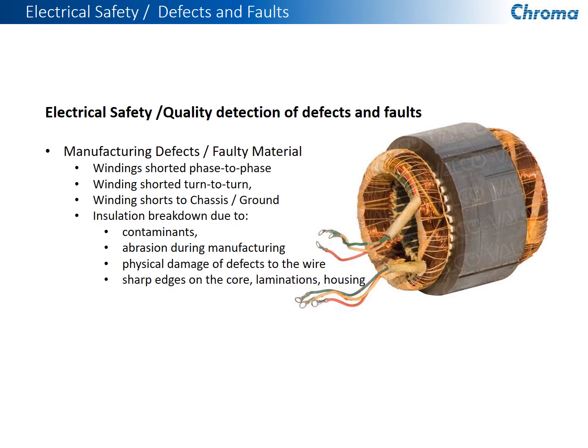So things that can happen during manufacturing defects, you can have everything from faulty material, the actual wire itself, its insulating material can have some kind of a fault in it. You can find material fault in the actual tape and the actual material used for insulation. There can be things like windings shorted phase to phase, internal windings shorted turn to turn, windings shorted to the chassis or ground or core, and various other types of breakdown due to some type of contamination within the windings, abrasion during manufacturing, physical damage, defects to the wire during storage, sharp edges on the core material, laminations and housing that can cut through the insulation.